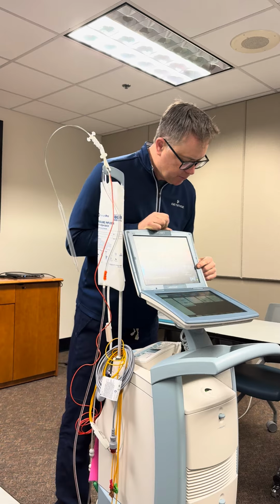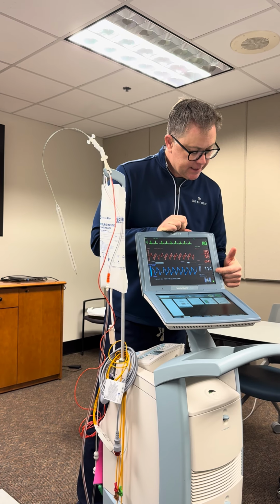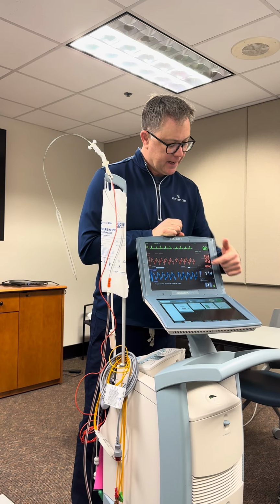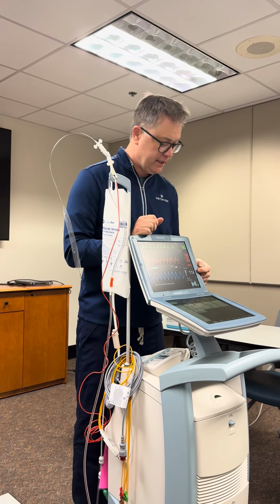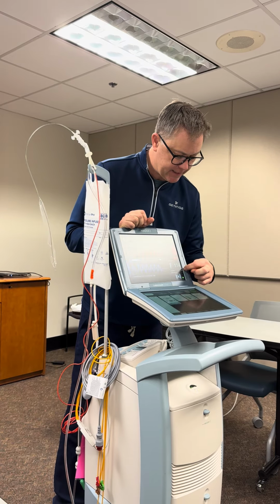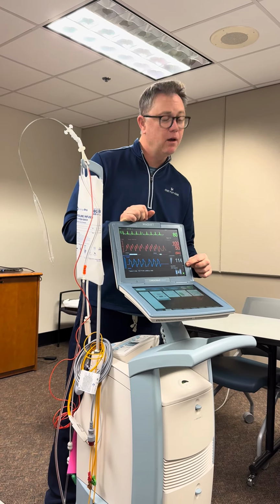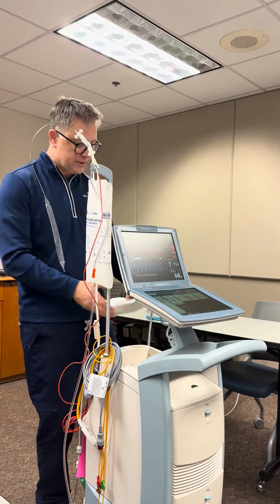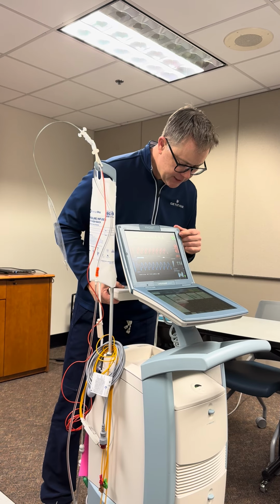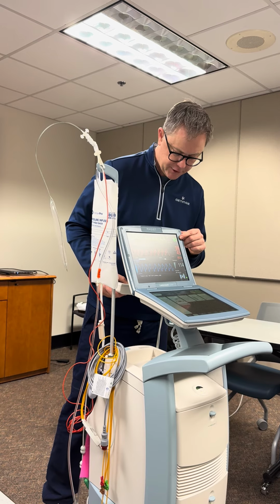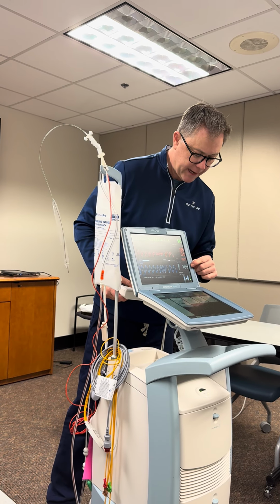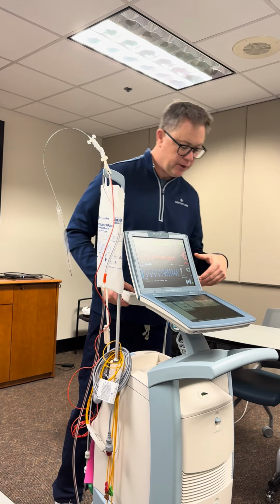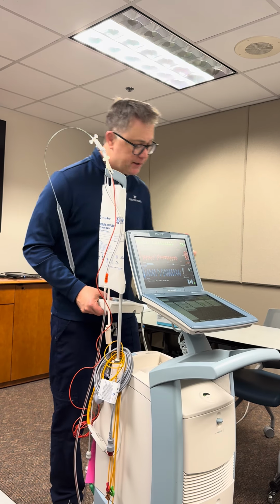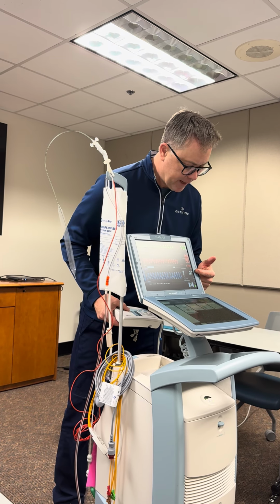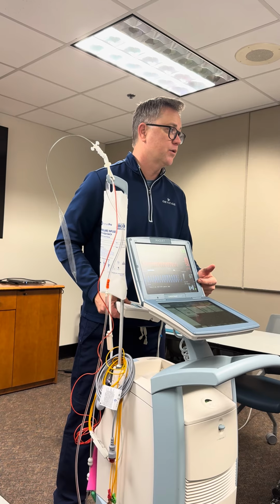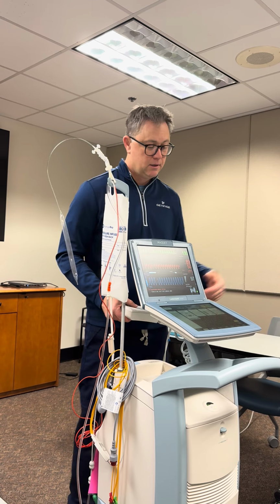Augmentation alarm. We were talking about that a little bit earlier. This patient has a diastolic augmentation of 114. That augmentation alarm has now set itself at 104, so roughly 10 below. If this patient's heart rate were to change, let's say it bounces up to 130, watch what happens to our augmentation. We don't have as much filling time, so we're not able to augment as well, and that's going to crash. We're now going to fall below what that augmentation alarm was originally set at, so it's going to trip the alarm.